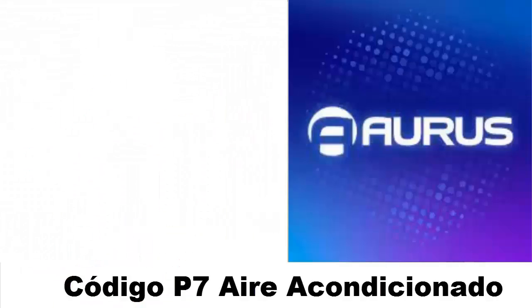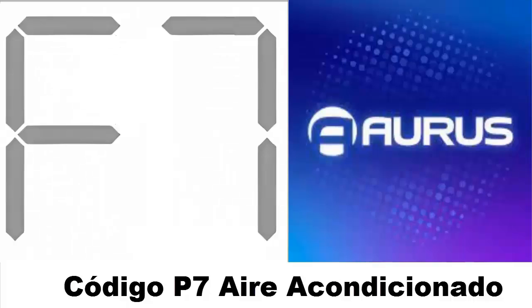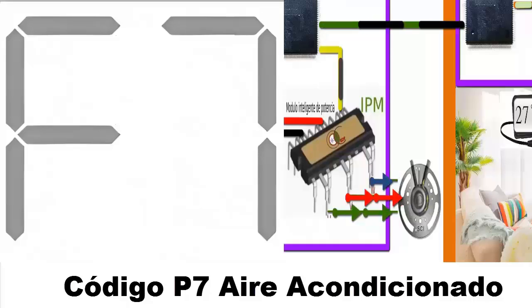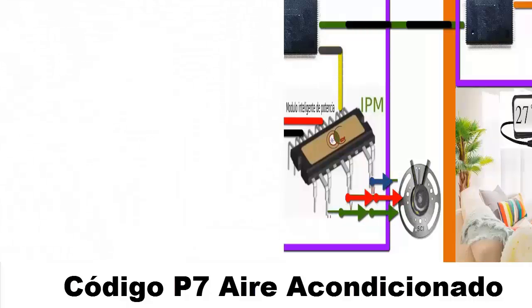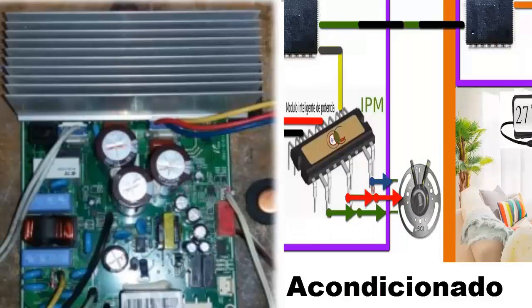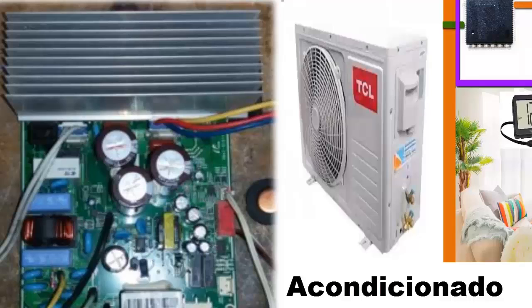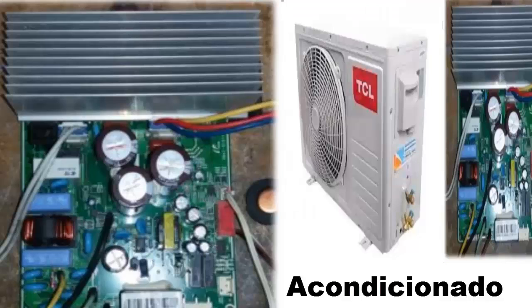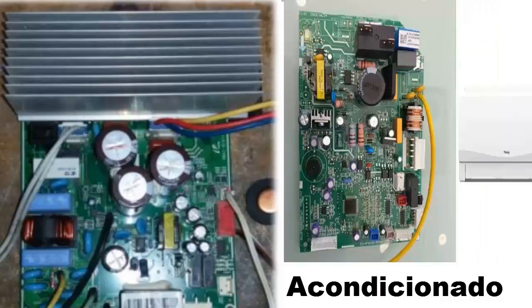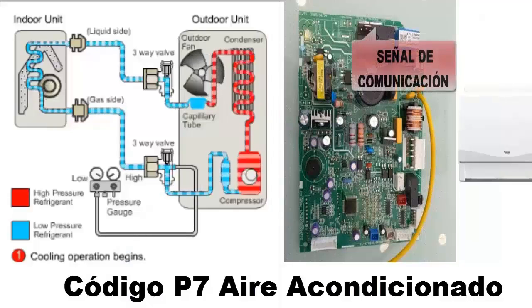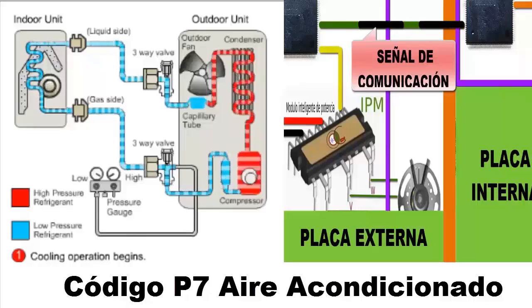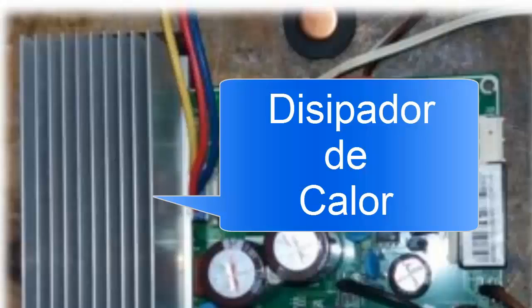For the Aurus air conditioning brand, the P7 code means a very high temperature in the outdoor unit's IPM module, which powers the compressor. This code can appear when the IPM module exceeds 95 degrees Celsius. For this condition to occur, several factors are necessary, such as poor contact between the heat sink and IPM, excess dirt on the heat sink, or excessive current in the compressor.